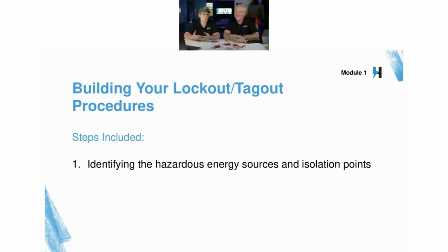So what does isolation point mean? This is where, for electrical, you are able to verify absence of voltage. For other energy sources, you'd be able to verify zero pressure - for pneumatic, steam, or any gases, you want to make sure there is no pressure. It's a valve that is shut off, a point where it can be locked out and isolated so there is no possibility of that energy reaching the machine where servicing or repair is being done.